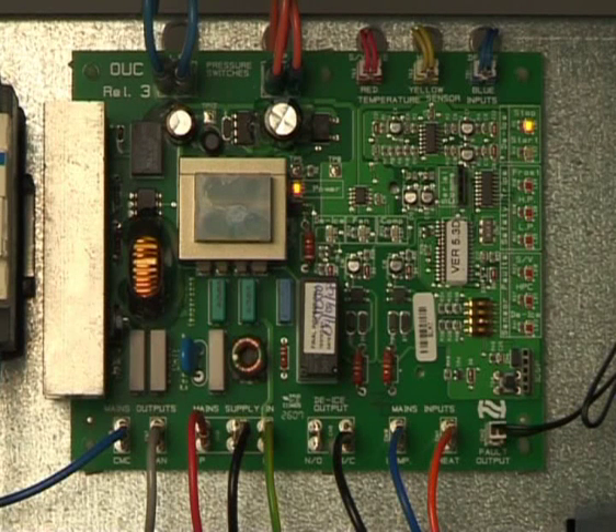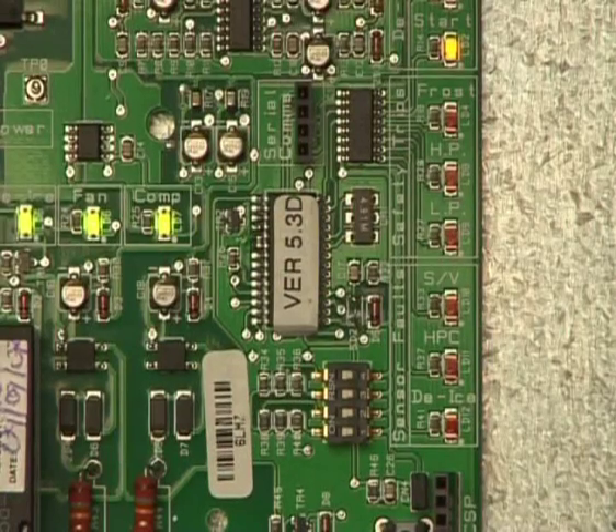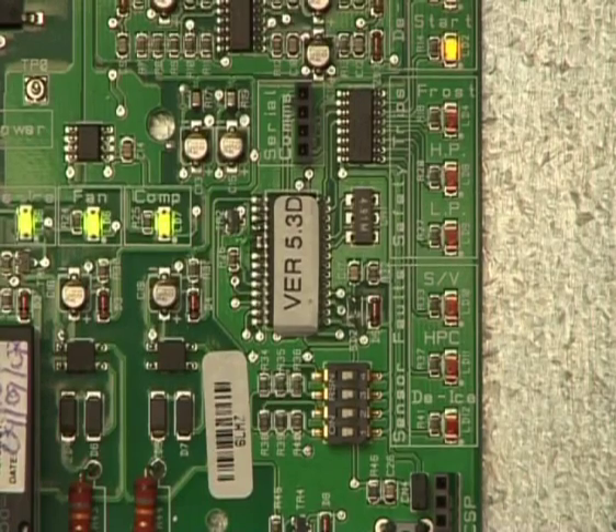Once the test function is complete, normal operation will be resumed. When in the heat cycle, it is possible to test and confirm that the de-ice function is working correctly. By pressing the test button for 2 seconds, the de-ice limit timer of 30 minutes is inhibited, and de-ice should occur whenever -4 degrees coil temperature is reached and the amber start LED is illuminated. This test should prove that the de-ice control is functioning correctly and that the sensor is reading correctly.